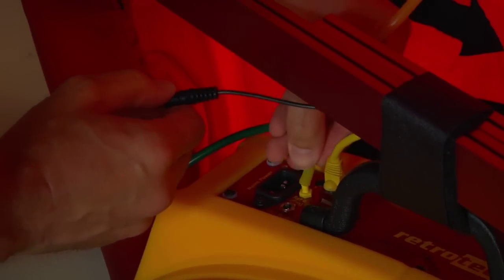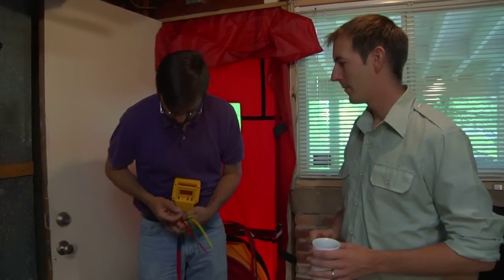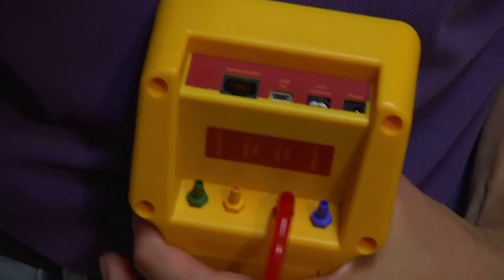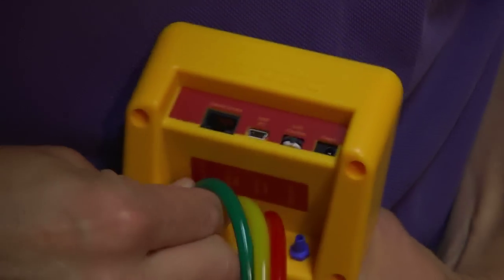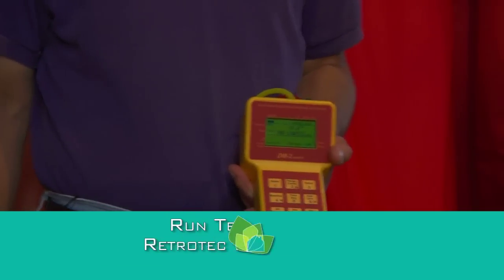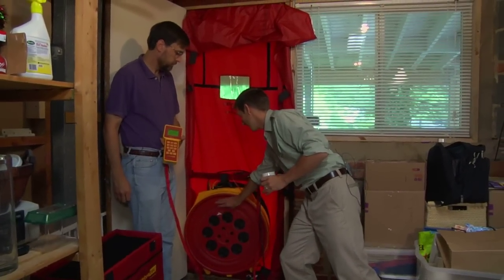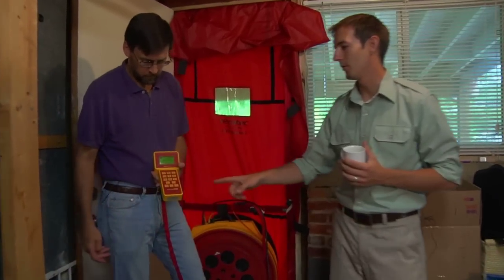Now the next step is to hook up the hoses. For the Retrotec, it's really easy — the yellow hose goes to the yellow nipple, and the red hose already goes outside. Then the control just goes in right there. For the manometer, it's very self-explanatory: green hose to green, red to red, yellow to yellow. Now that the hoses are hooked up, you want to make sure that the blower door is completely sealed off. For the Retrotec, make sure all of these are on and nice and tight. Once you've done that check, it's time to turn on your manometer and get your blower door running.